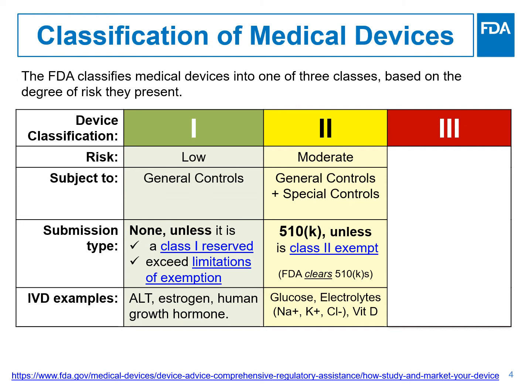That is basically the demonstration that the new device, compared to a predicate device, has the same intended use and the same technological characteristics, or it has the same intended use and the differences in technological characteristics do not raise different questions about safety and effectiveness. This means that the manufacturer provides evidence to demonstrate that the device to be marketed is at least as safe and effective, or substantially equivalent, to a predicate. And how do we define predicate? For FDA, a predicate device is a legally marketed device that has been cleared through the 510K process.